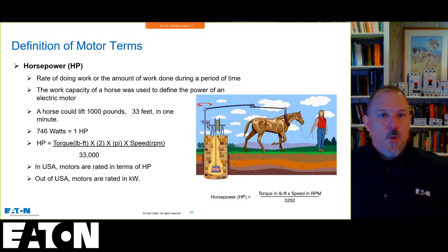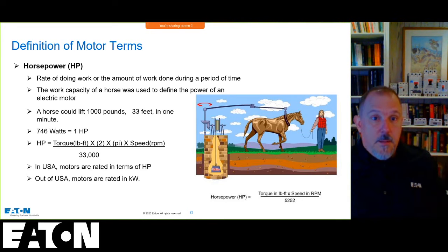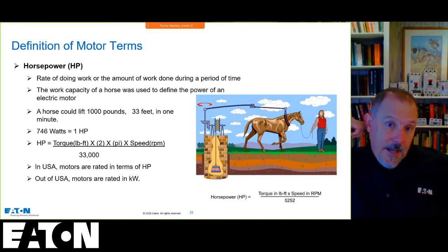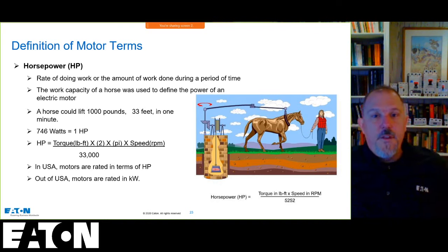So horsepower, the rate of doing work, it's the amount of work that's done, and it's the capability of that motor at its shaft. Horsepower is defined in, if you consider those five parameters on the previous slide, torque and speed help you determine the horsepower output. And the equation for that is torque times 2 times pi, I couldn't figure out in Microsoft PowerPoint how to get that pi symbol, but in any case, times the speed, over 33,000. And if you work that down, you'll get torque times speed over 5252. That's probably an equation that you are more familiar with.